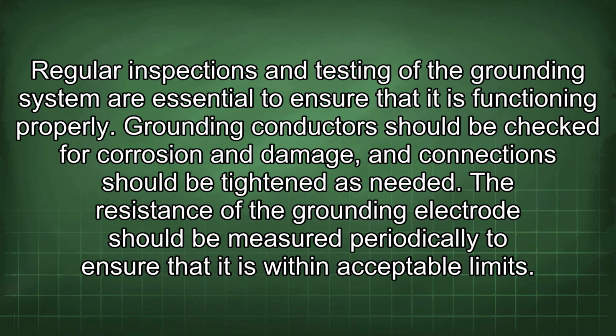Regular inspections and testing of the grounding system are essential to ensure that it is functioning properly. Grounding conductors should be checked for corrosion and damage, and connections should be tightened as needed. The resistance of the grounding electrode should be measured periodically to ensure that it is within acceptable limits.